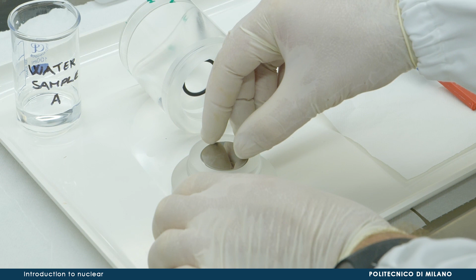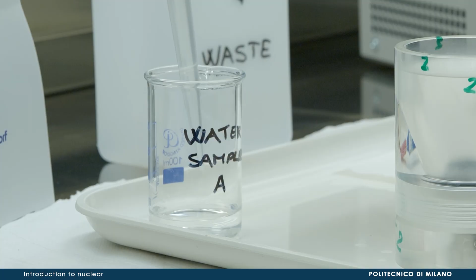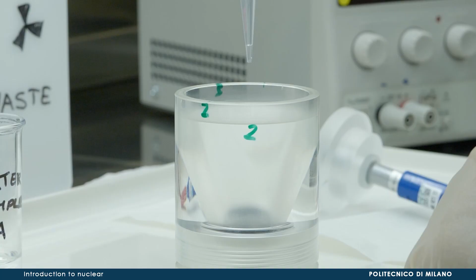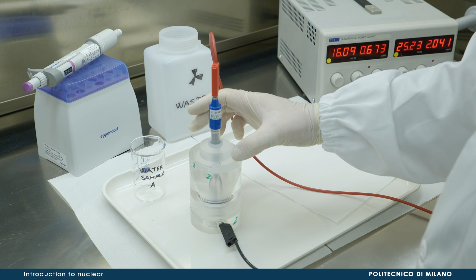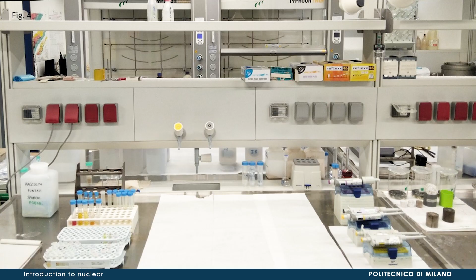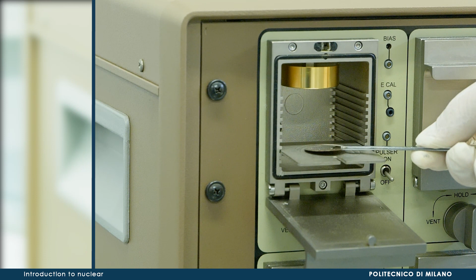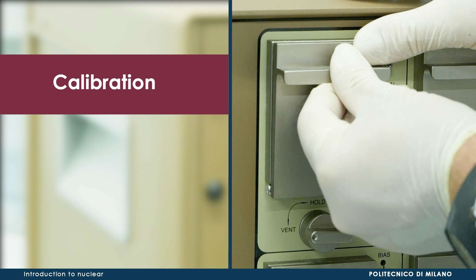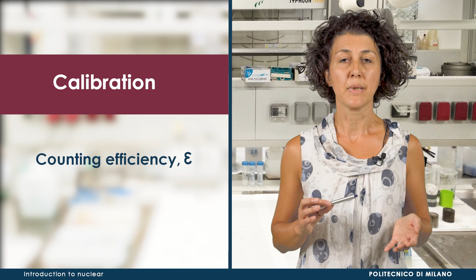At this point, the sample solution has to be prepared for uranium measurement by alpha spectrometry. This is done by electrodeposition. This step, which requires about 2 hours, consists in electrolytic deposition of uranium onto stainless steel planchets. For quantifying the uranium concentration, it is necessary to calibrate the alpha spectrometer by a suitable calibration source, evaluate the counting efficiency, and register the background in the region of interest.